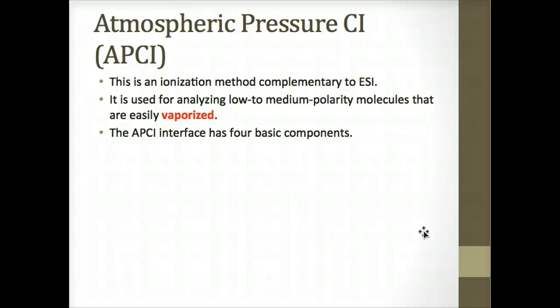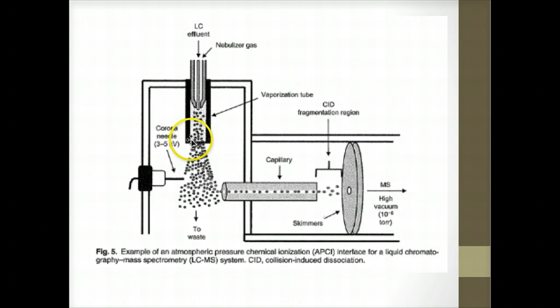Here's atmospheric pressure chemical ionization. This is an ionization method complementary to electrospray ionization, very similar. So APCI is used for analyzing low to medium polarity molecules that are easily vaporized. It is also best that analytes do not contain acidic or basic sites. Compounds can be moderately volatile. And the atmosphere pressure chemical ionization interface has four components: the nebulizer, vaporization tube, the corona needle, and the desolvation module. Very similar to what we've seen before. The liquid mobile phase enters the nebulizer and flows through the needle assembly. And the nebulizer blows high pressure nitrogen around the needle and blasts the mobile phase into a fine aerosol. So it enters in right here, gets blasted, and goes through this corona needle through the capillary again into a chamber for CID to occur.